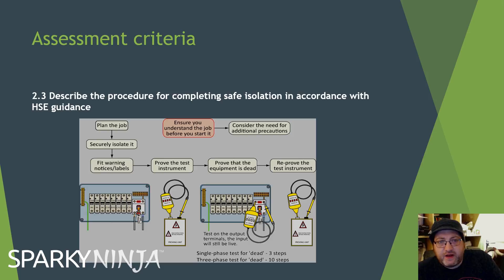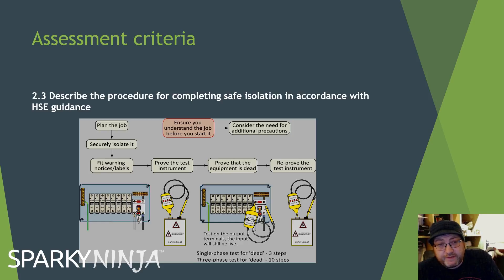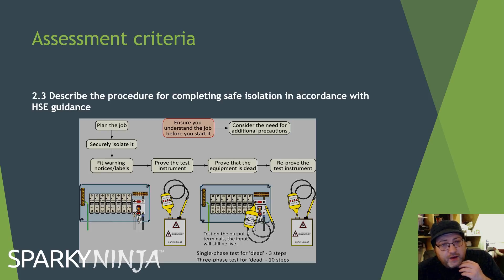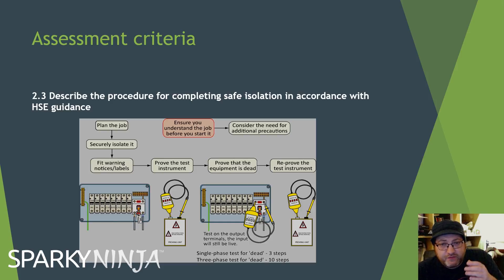This diagram is the common one — if you Google it, you'll find similar examples. It always starts with planning the work effectively, then securing isolation. You may need labeling or drawings to identify the point of isolation — find it and secure it. The method of securing it is a suitable lock-off device, labeled, etc. Fit warnings and labels, then grab the proving unit, test it, prove it. You need to be able to write down the process.